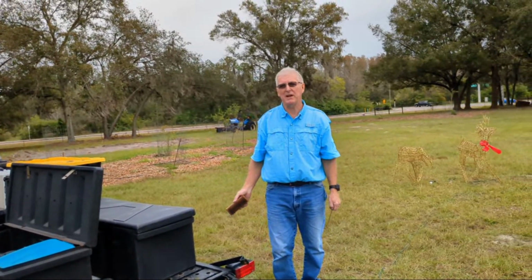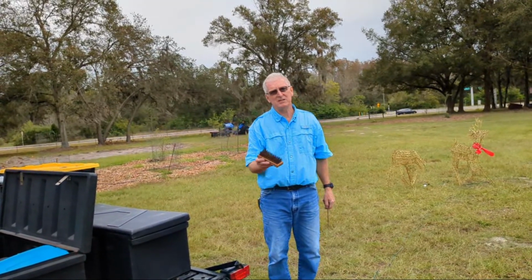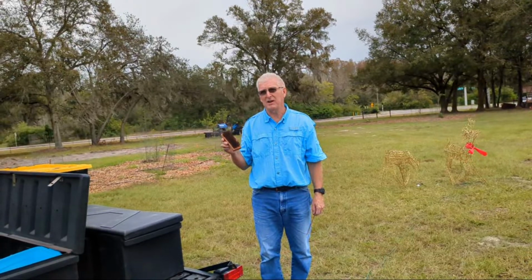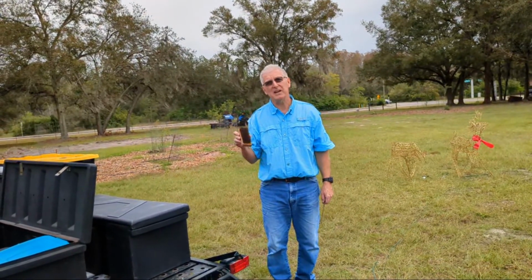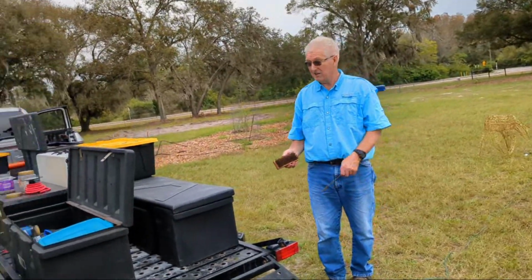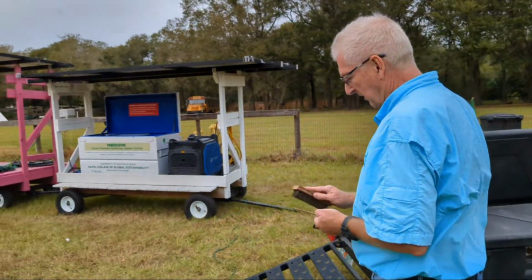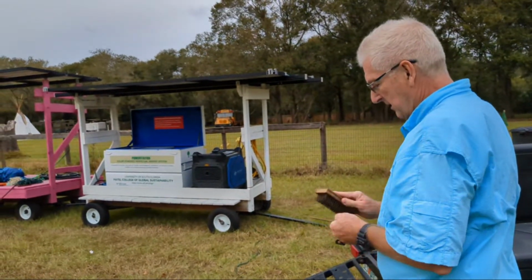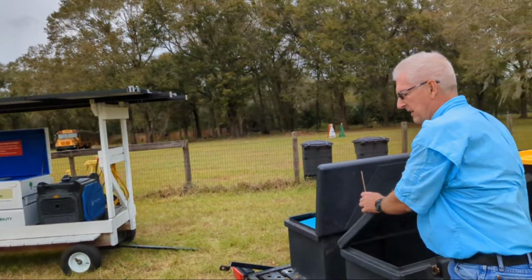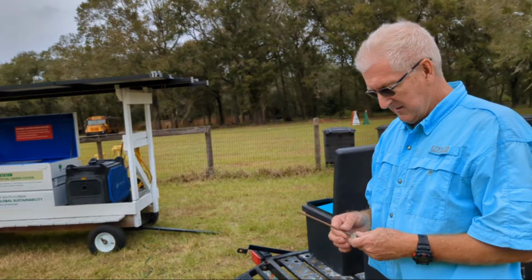So that's why we typically have mobile switches or mobile systems, and we have stationary systems. How we deal with grounding and bonding is particular to each case. You have a unique situation here where you have a system that works connected to the grid and then on its own when it's off grid, and that creates some particularly complex problems which we're going to try to fix. You're saying there is a setting in the inverter that one could attend to and say, I'm going off grid. I check it now so that it's off grid, and then I go back to the trailer.